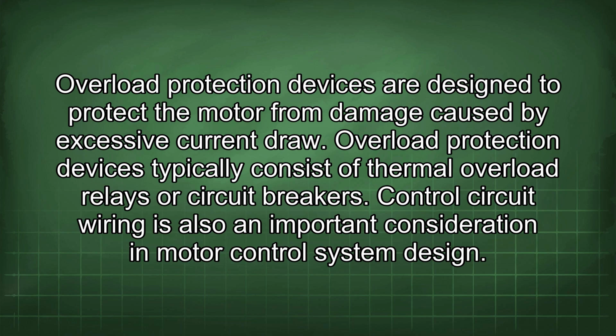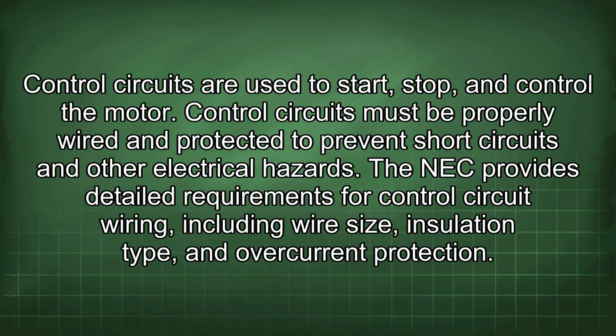Overload protection is another important aspect of motor control system design. Overload protection devices are designed to protect the motor from damage caused by excessive current draw. Overload protection devices typically consist of thermal overload relays or circuit breakers. Control circuit wiring is also an important consideration in motor control system design. Control circuits are used to start, stop, and control the motor. Control circuits must be properly wired and protected to prevent short circuits and other electrical hazards. The NEC provides detailed requirements for control circuit wiring, including wire size, insulation type, and overcurrent protection.